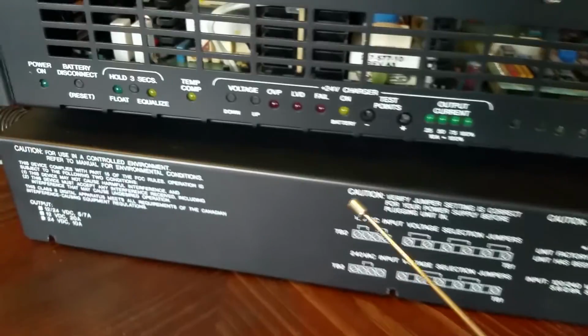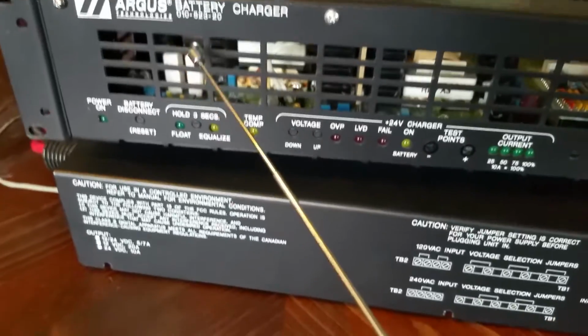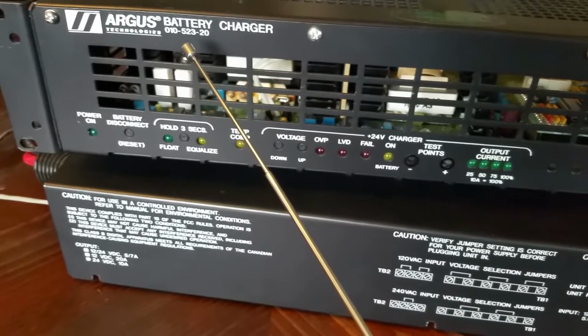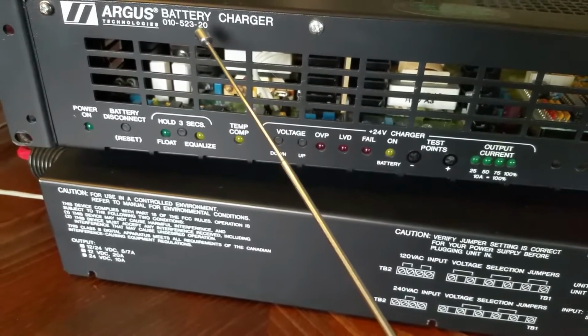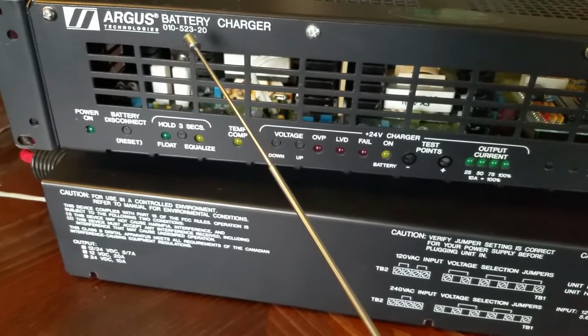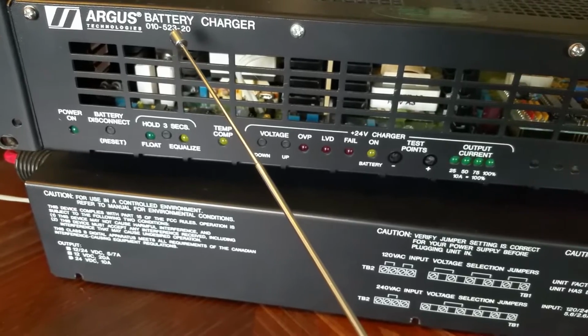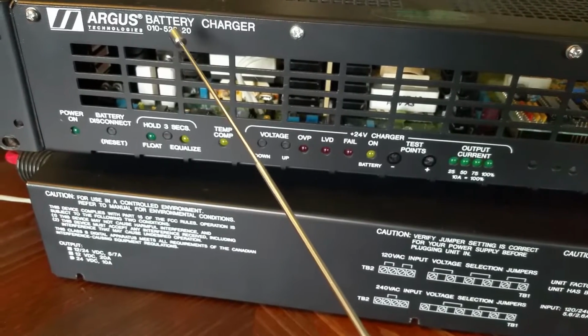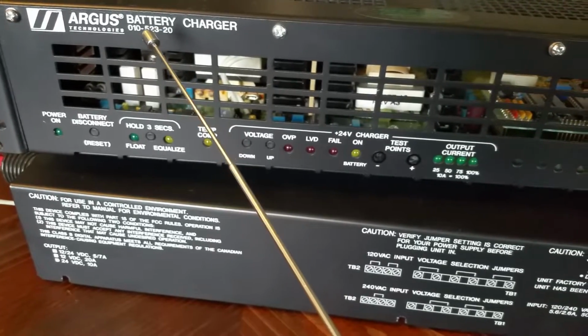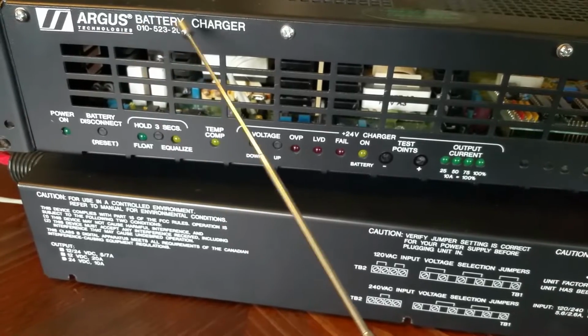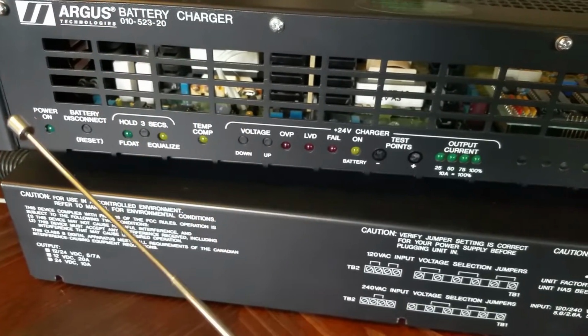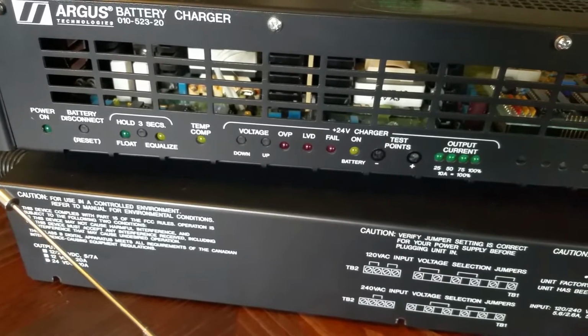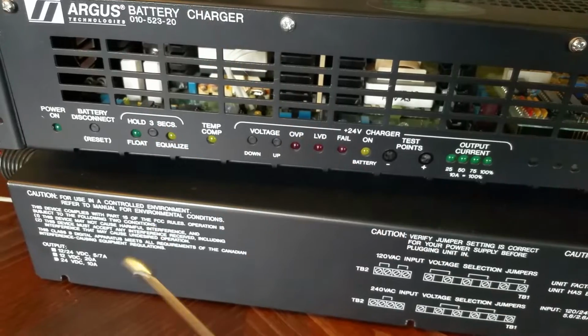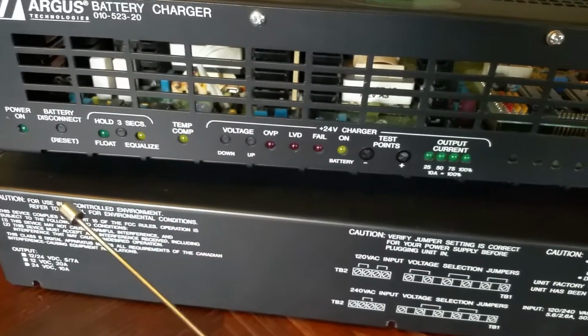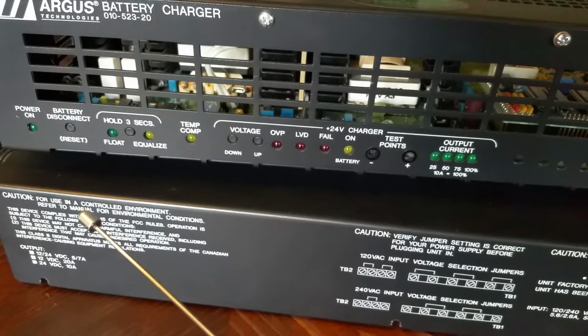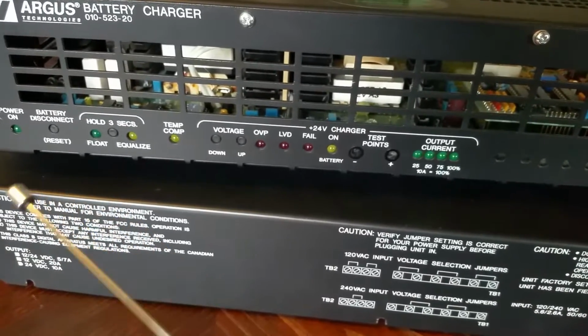For example, when you run this device on a 12 volt system, you get 20 amps going to the battery. Remember, when you go parallel, you gain more amps at low voltage, like a 12 volt system. When you go with 24 volts, the higher the voltage, the lesser the amps — so this device only charges at 10 amps there. If it were 48 volts, it would approximately be maybe 5 amps or so for charging the battery — higher volt, lower amperage.